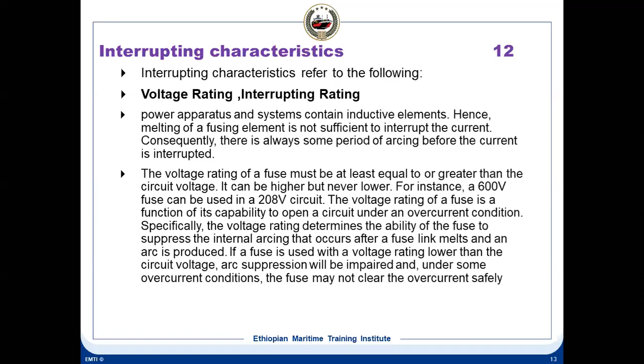How are fuses rated? Fuses are rated by current, voltage, and breaking capacities, and whether they're designed to operate on AC or DC. There are two different kinds, AC fuses and DC fuses. The current rating of a fuse is the current it can carry for a definite time period without opening. Voltage rating relates to the ability of the fuse to function and extinguish the internal arc when it opens.